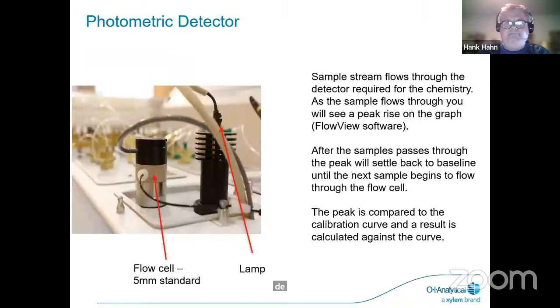We did some work with the expanded range detector with the sensitivity. It can detect very small changes in the signal without increasing the gain. And this allows for detection of low concentrations. The photometric detector allows the sample stream to flow through the detector required for the flow chemistry. As the sample flows through, you'll see a peak rise on the graph with our FlowView software. After the sample passes through, the peak will settle back to baseline until the next sample begins to flow through the flow cell. The peak is compared to the calibration curve, and a result is calculated against that curve.